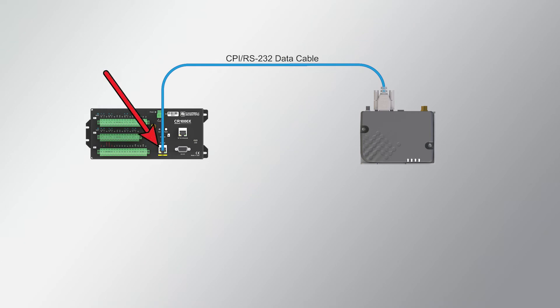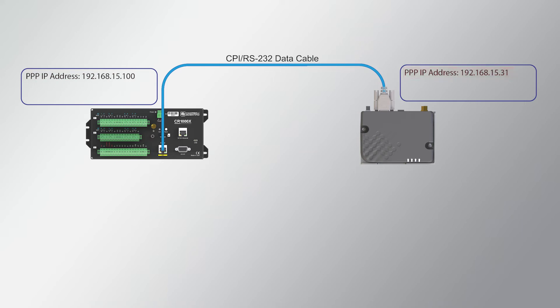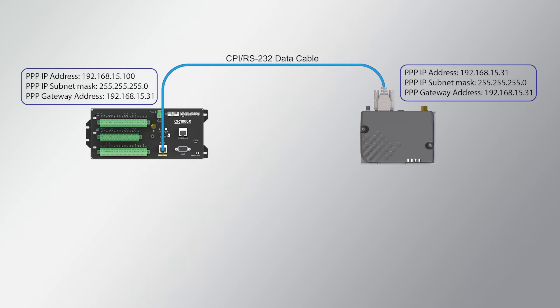In this example, a CR1000X data logger is connected to the RV50X using PPP. A CPI to RS-232 cable is attached from the CR1000X CPI port to the RV50X RS-232 serial port. The CR1000X is automatically assigned an IP address of 192.168.15.100 by the RV50X's DHCP server, while the RV50X has a static IP address of 192.168.15.31. Both devices receive a subnet mask of 255.255.255.0, and the CR1000X is assigned a gateway address of 192.168.15.31 — the IP address of the RV50X — as the modem will communicate with hosts outside the local network.